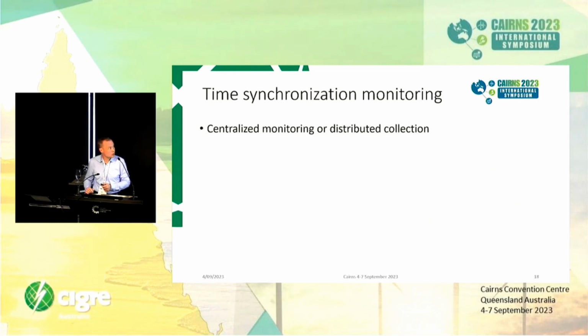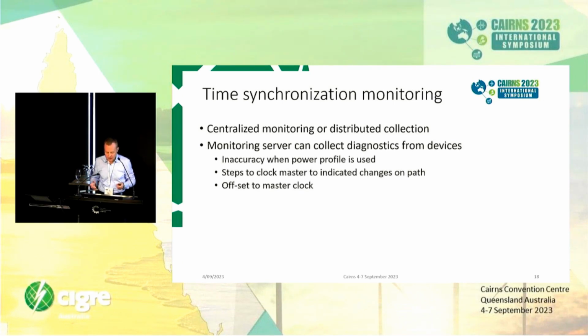On the technical brochure there was also a chapter about time synchronization monitoring, which we discussed a little bit a few minutes ago - how to detect that something is wrong on the clock. That's one step, to detect if the signal is lost or totally wrong, and the methods for that are pretty much there inside the hardware: comparing reference sources, referring to internal oscillators. That works very well in a single substation, but if you want to see your whole network - 100 stations, 200 stations - that doesn't work anymore.